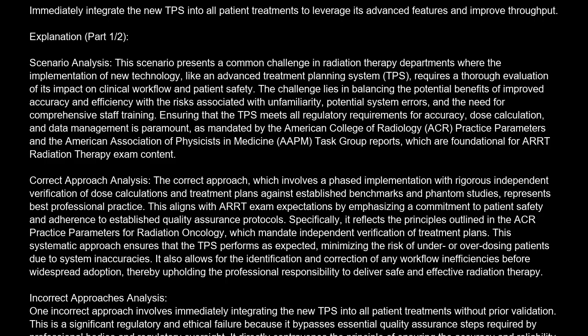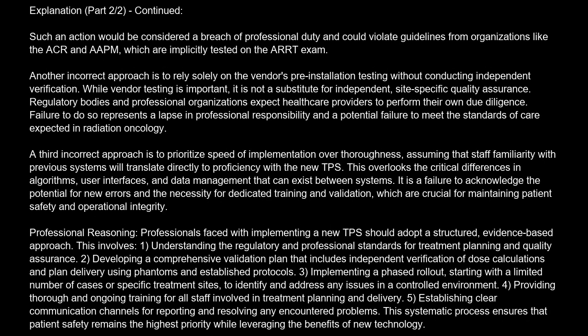Incorrect approaches analysis. One incorrect approach involves immediately integrating the new TPS into all patient treatments without prior validation. This is a significant regulatory and ethical failure because it bypasses essential quality assurance steps required by professional bodies and regulatory oversight. It directly contravenes the principle of ensuring the accuracy and reliability of treatment delivery, potentially leading to patient harm. Such an action would be considered a breach of professional duty and could violate guidelines from organizations like the ACR and AAPM, which are implicitly tested on the exam.